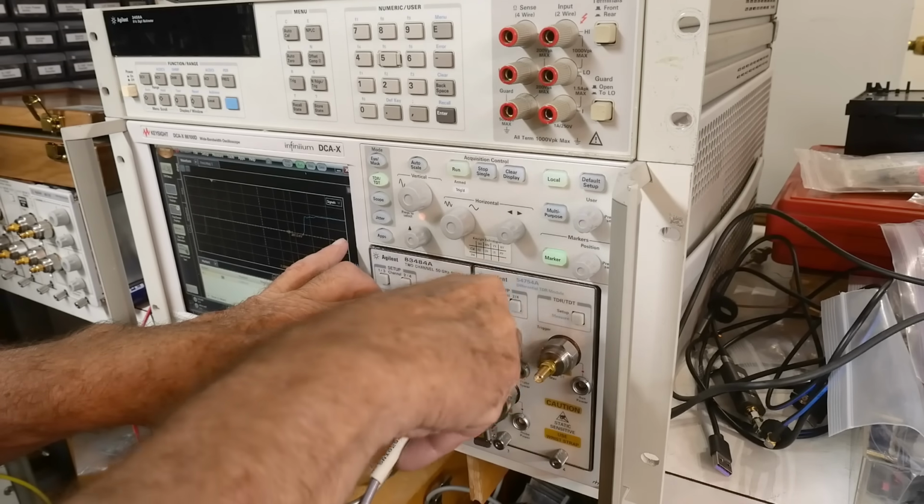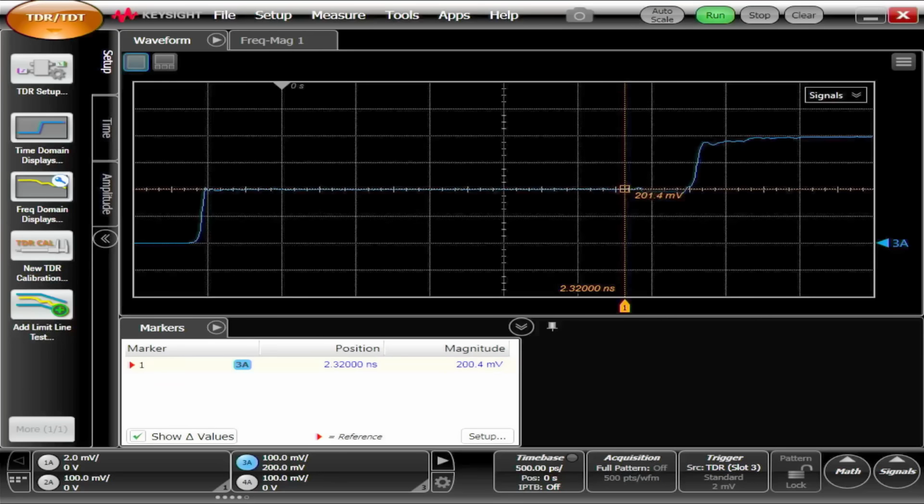All right. So I think you can see we left the marker where the end of that cable was, and now we've got some additional length right here. Well, that's the length of our little board, so we can actually measure the length of that little board, okay? And then we get a big discontinuity change here, because it's an open again, right?